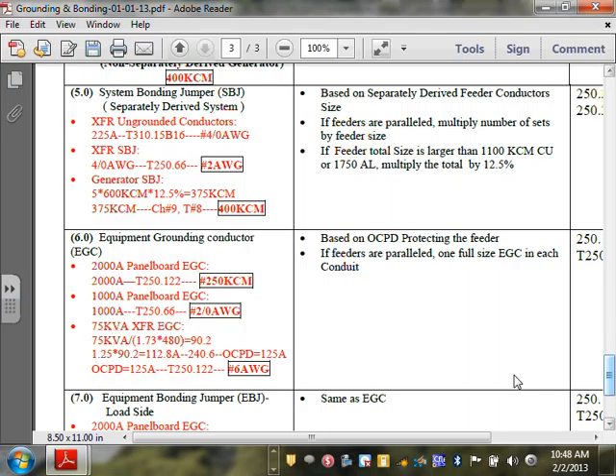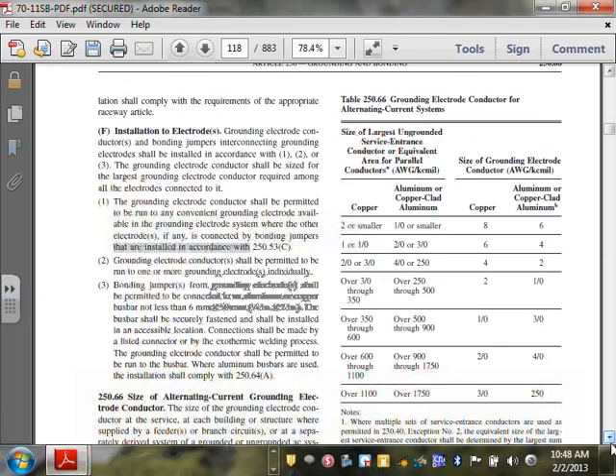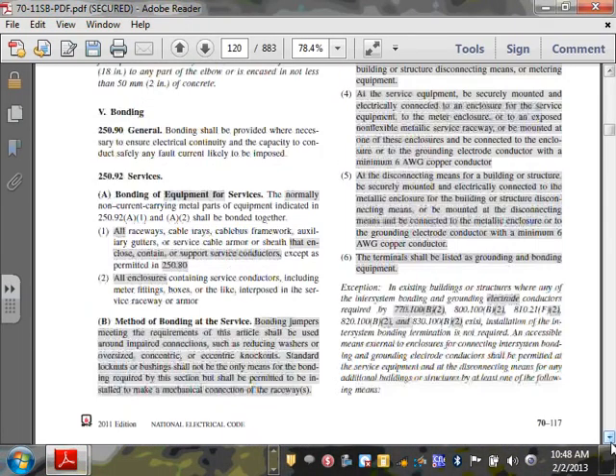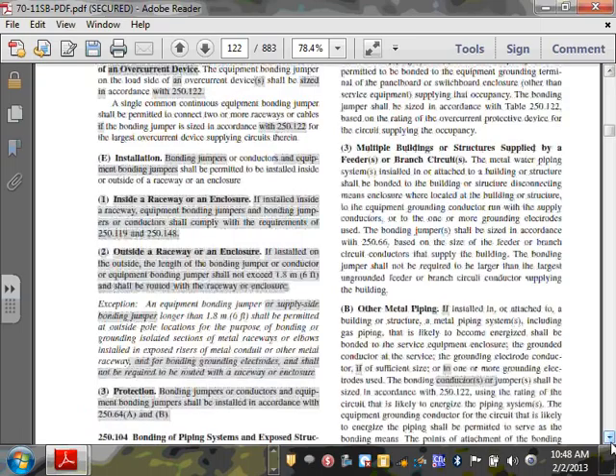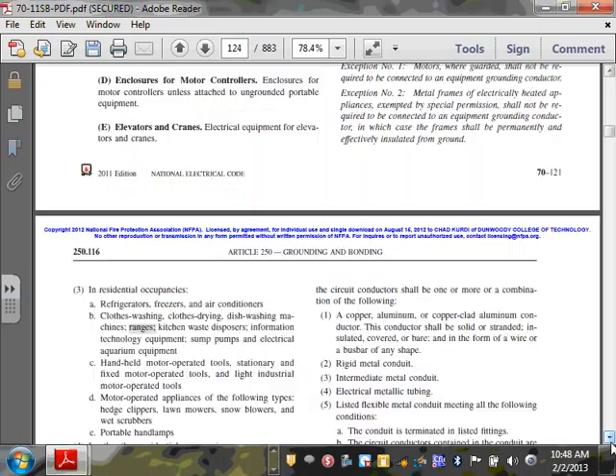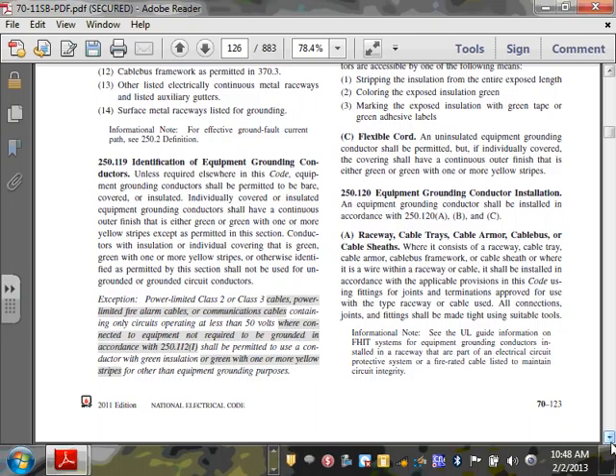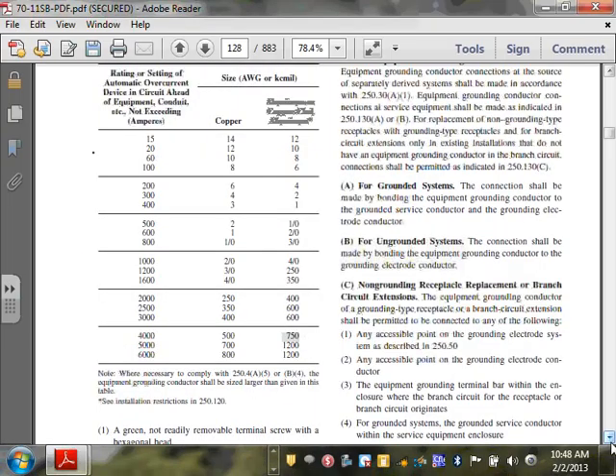So you go to 2,000 amp, 250.122. If you go to 250.122, very quick, right here. And for a 2,000 amp, let's go all the way to 2,000 amp, jumping to these tables. How much did you come up with? There you go. So 2,000 amp, you are familiar with this table. Here's my 1,000 amp. Did they size for 2,000 amp? Oh, there's 1,000 there too. Okay, that's what I thought.